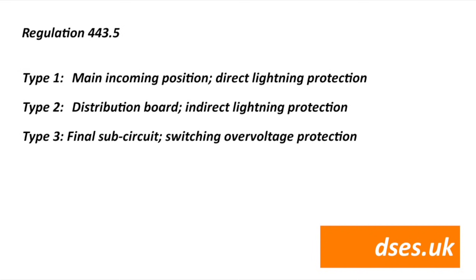Combination units can be sourced, and according to the manufacturing blurb supplied with my model, a Type 2 SPD is OK for installations fed by underground cables, but a Type 1-2-3 combination device would be required for installations fed by overhead power lines, regardless of whether that's single or three-phase. I'll be playing with a Type 2 device here today as I'm on an underground PME connection, so this is what I'll be installing here.